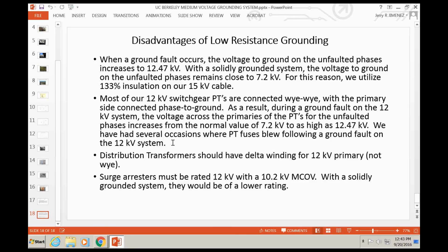Go ahead, Jerry. So I'll also mention some of our 12 kV switchgear uses what are called open delta PT arrangements, where you only have 2 PTs, and one of them is connected phase A to phase B, and the other one's phase B to phase C. Now those are not vulnerable to these ground faults in terms of fuses blowing, so they do just fine during these ground faults. It's only the PTs that are connected grounded Y to grounded Y that tend to blow fuses.